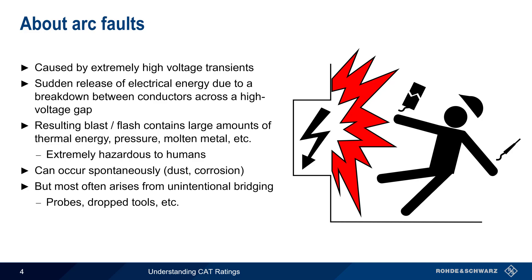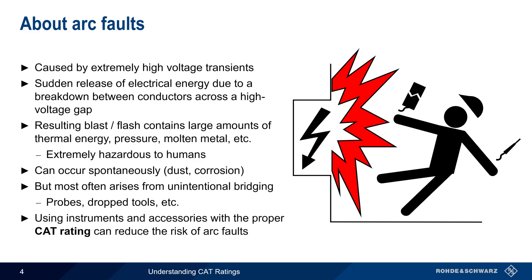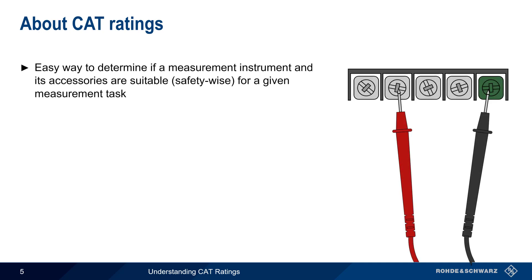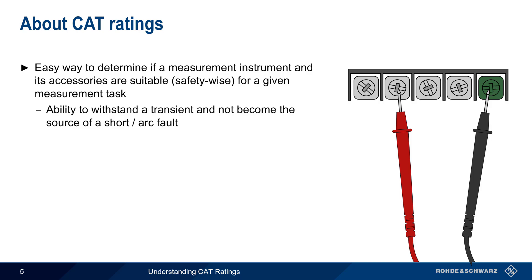The risk of arc faults can be reduced by using instruments and accessories with appropriate CAT ratings. CAT ratings are a clear and easy way to determine if a measurement instrument and its accessories are suitable, in terms of safety, for a given measurement task. Safe in this context refers to the measuring instrument's ability to withstand a given transient and not become the source of a short and or an arc fault. Another way of saying this is that CAT ratings help answer the question: is it safe to use this instrument in this measurement environment?